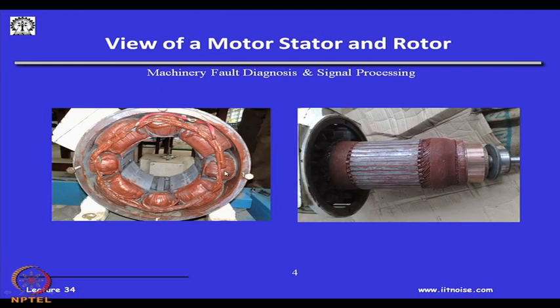With this, let me just give you a pictorial view of a motor we just opened up in the lab so that you all are able to see. This is how an electrical motor looks inside. This is the frame of the motor. This is the stator. Once you give electrical supply to this, there is a magnetic field in this. Because of this magnetic field, there will be flux induced in the rotor. The rotor is nothing but again a series of conductors put together. Each one is a conductor, and these are very soft material because they need to have good magnetic properties. And this is the rotor shaft, which actually sticks out of the motor. And you can see one bearing at this end, and there is another bearing at the other end.